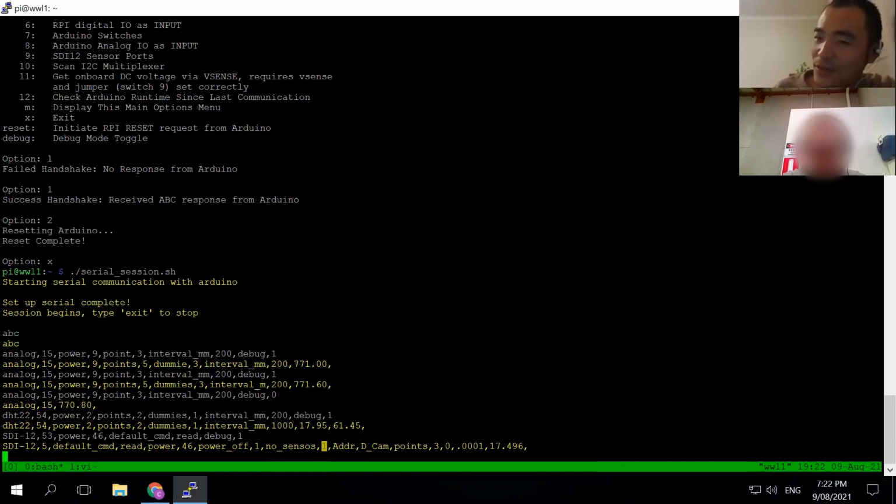But again, I normally don't put all the sensors into one digital channel, because one of the things we find, not very commonly, but it's possible, is that one of the sensors gets short-circuited. And if that's the case, then all the sensors in that digital channel have to be disabled, because if you don't do that, the rest of the system wouldn't work. So this also shows the importance of having the power separately. Because let's say you have a data logger that has 100 sensors, and one of the sensors is short-circuited, you basically lose all of them. Exactly, and you still want a successful project at the end of the day. No, that makes sense.